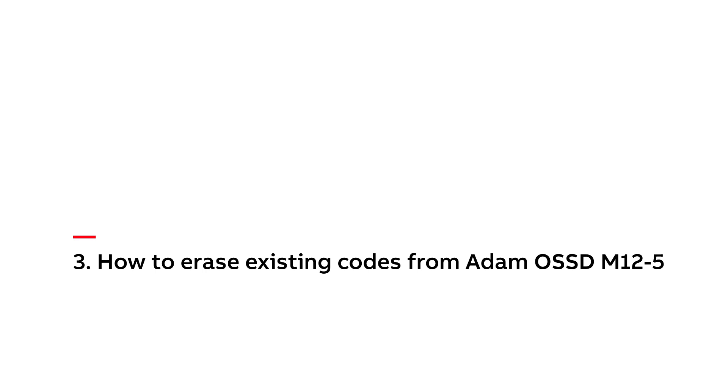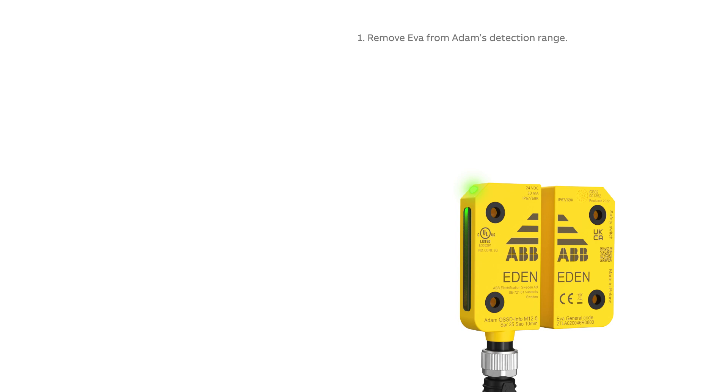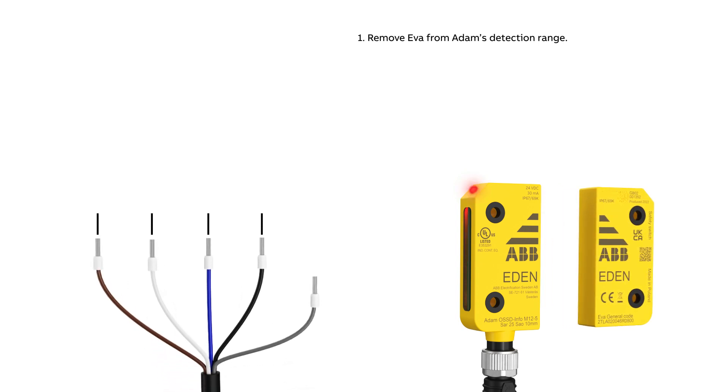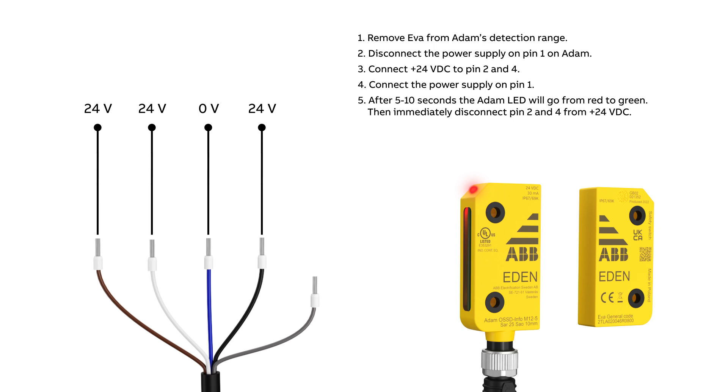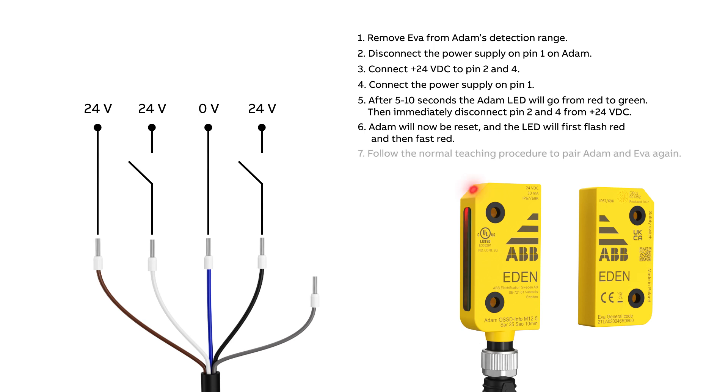How to erase existing codes from Adam OSSD M12-5. Remove Eva from Adam's detection range. Disconnect the power supply on pin 1 on Adam. Connect 24 volts to pin 2 and 4. Connect the power supply on pin 1. After 5 to 10 seconds, the LED will go from red to green. Then immediately disconnect pin 2 and 4 from 24 volts. Adam will now be reset and the LED will first flash red and then fast red. Follow the normal teaching procedure to pair Adam and Eva again.